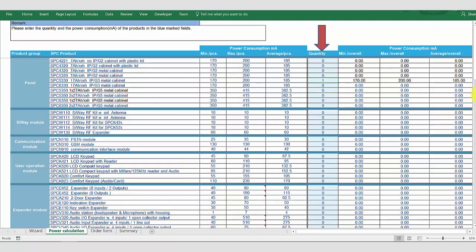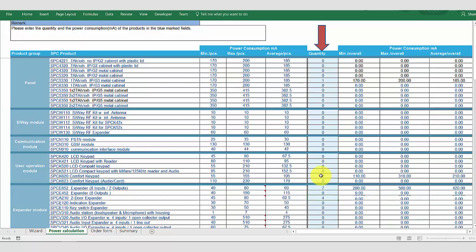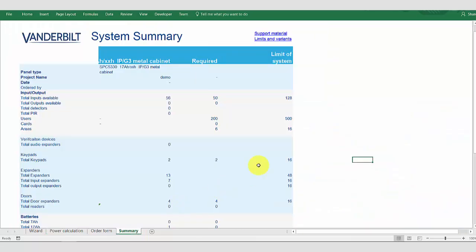We will now increase our system with a number of inputs required. We will add on seven expanders, add two keypads, and add four door controllers to our system. We will also add a GSM module. Returning to the summary, we can see we have sufficient inputs, the number of users is sufficient, and the system will support the number of keypads, so all is well.